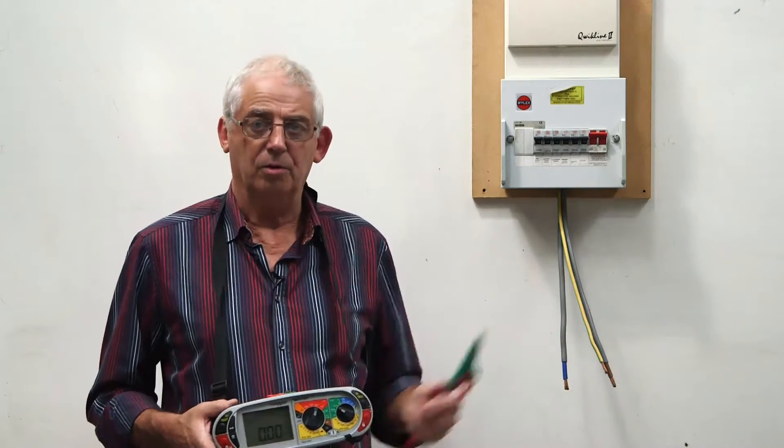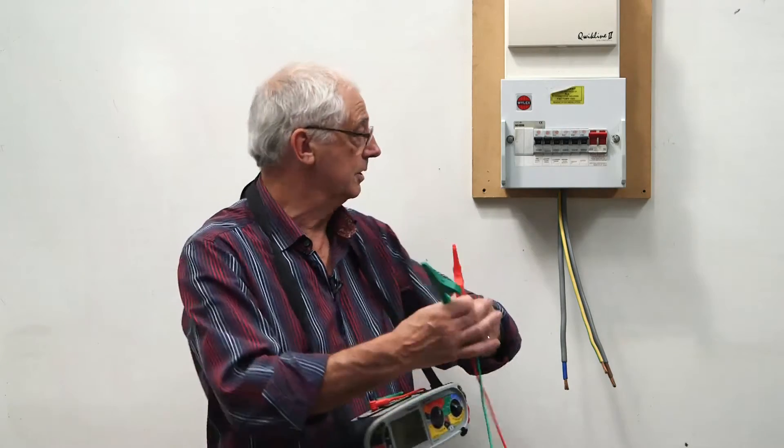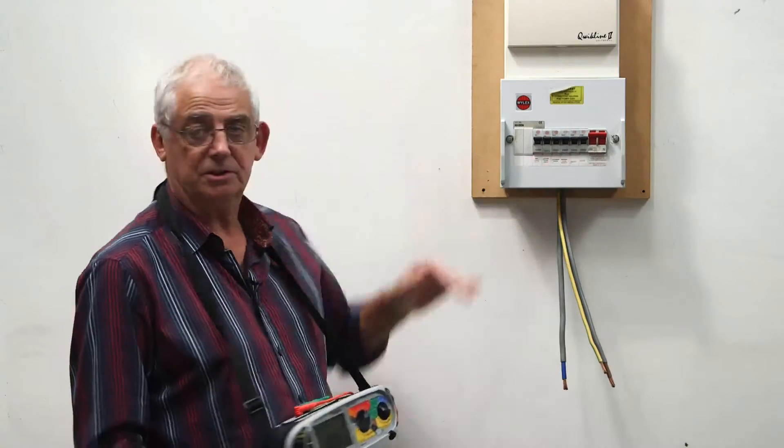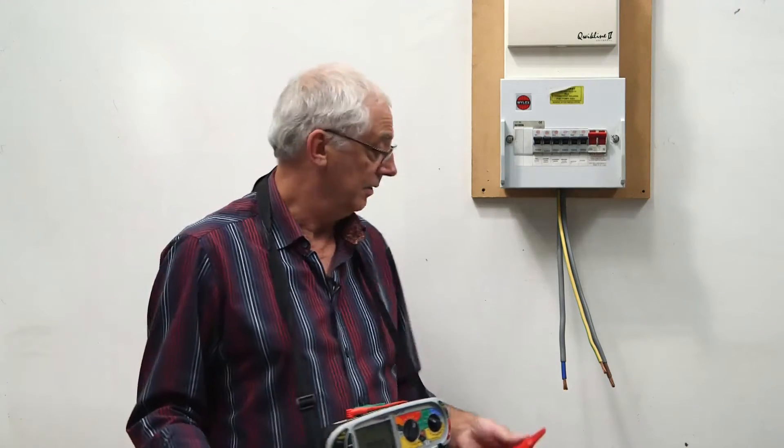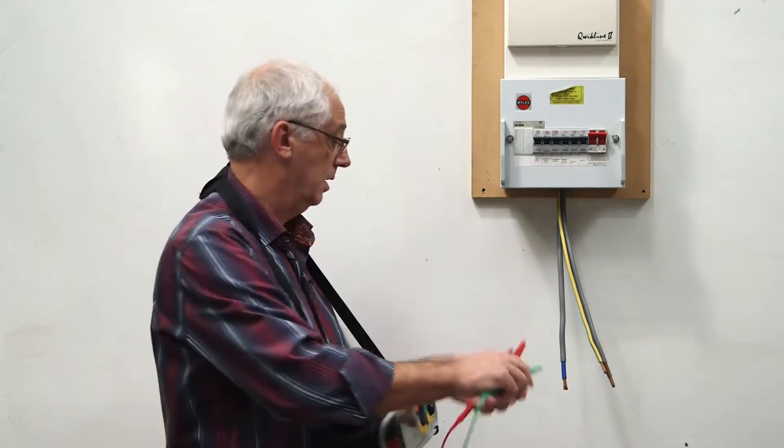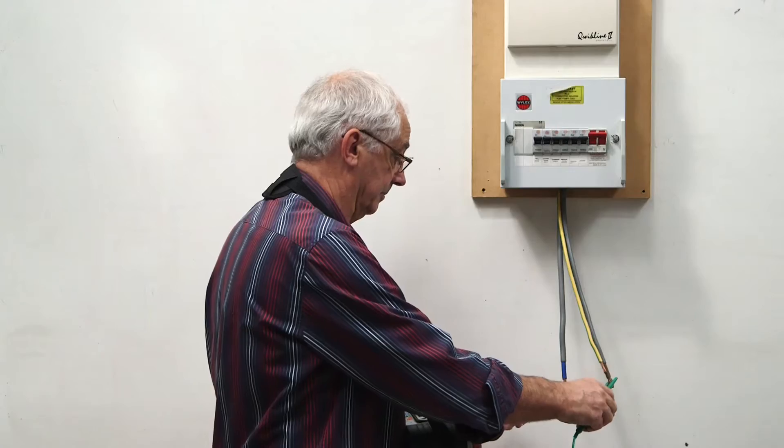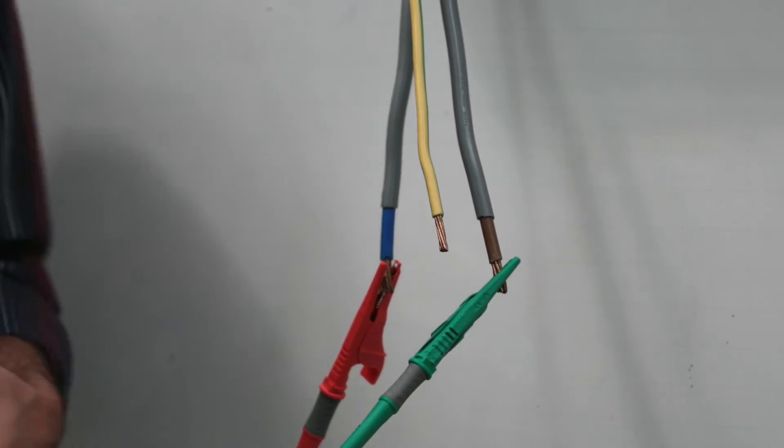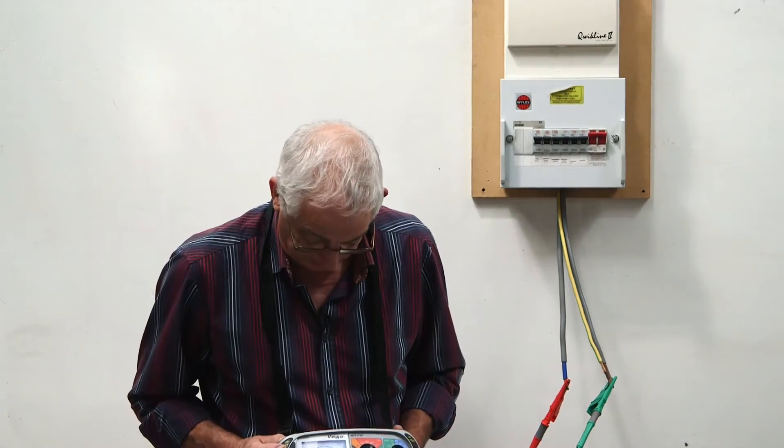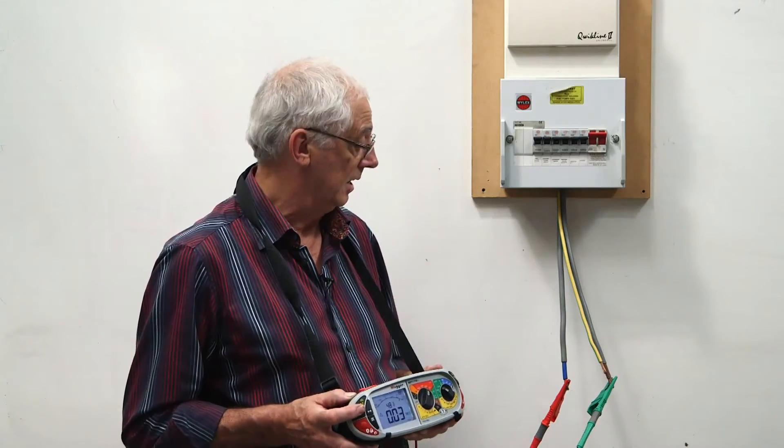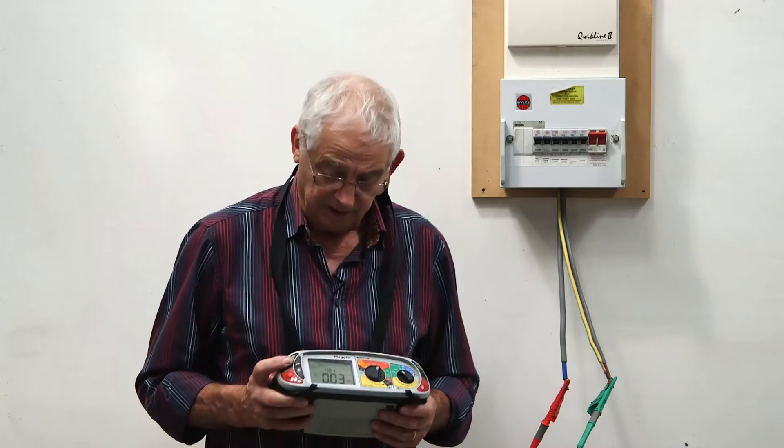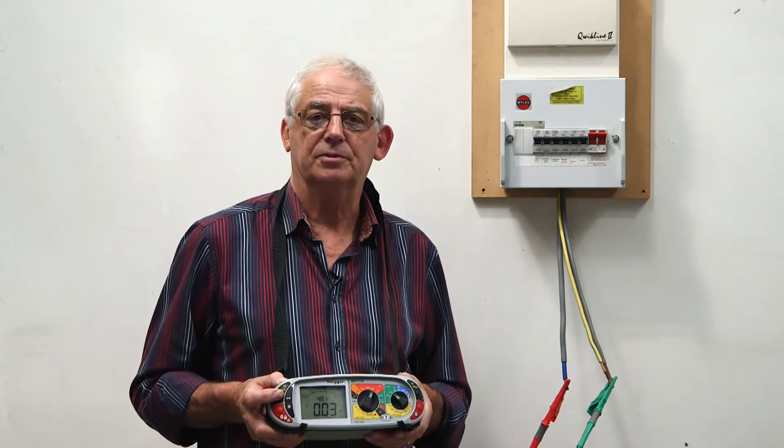Once I've carried out all of that, I need to make sure that all of these switches are turned on. I know the instrument's working and I need to test first of all between live conductors. Push the button and I've got a reading of 0.03 between live conductors. That's telling me that that's a low resistance fault.